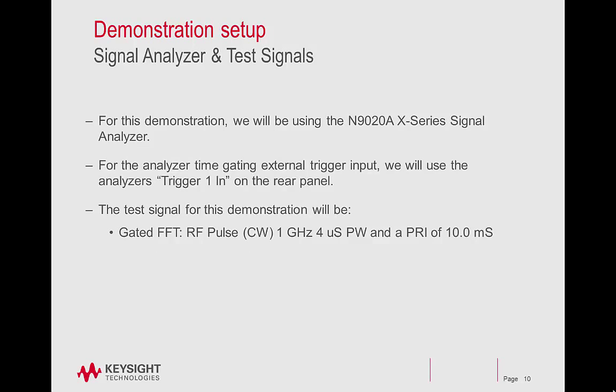For this demonstration, we'll be using the N9020A X-Series Signal Analyzer. For the analyzer time-gating external trigger input, we will use the analyzer's Trigger 1 In on the rear panel. The test signal will be an RF pulse CW 1 gigahertz with a 4 microsecond pulse width and a pulse repetition interval of 10 milliseconds.